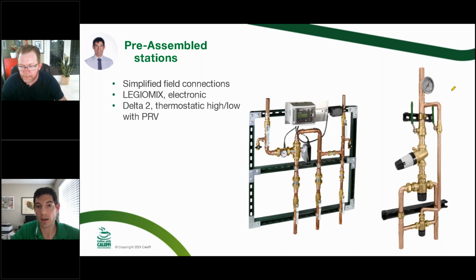And we also have that in the high-low mixing valve. We call that the Delta 2, that would have the piping correct for a small thermostatic and a big thermostatic with the PRV in the middle. You still have to set the PRV in the field, but it's going to be piped correctly. So those are nice selections for engineers too, if they just want to say, I want it to be exactly like this. It may or may not be at the end of the day, but this gets you started with all the most important components in the right places.